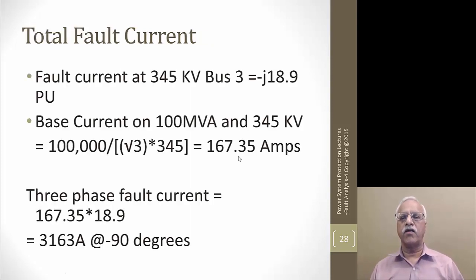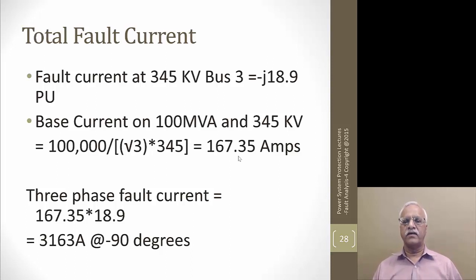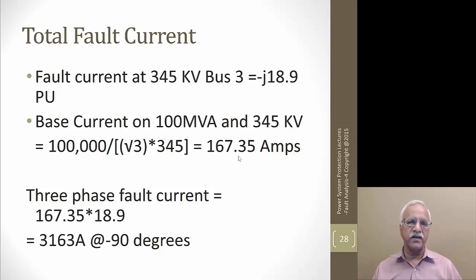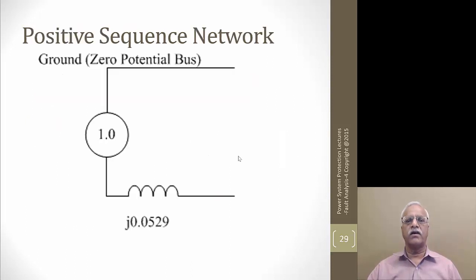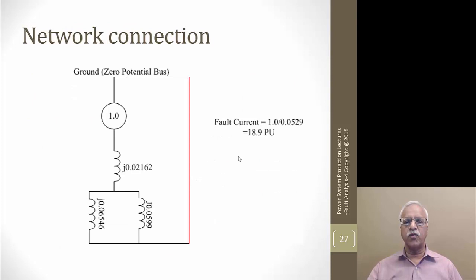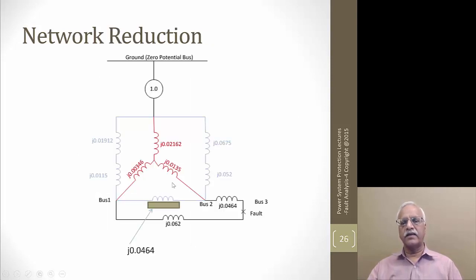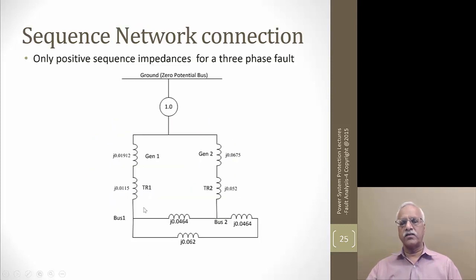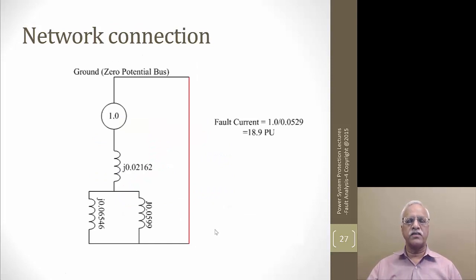The total fault current at 345 kV is -j18.9 per unit. The base current on 100 MVA at 345 kV is 167.35 amperes. So the three-phase fault current is 167.35 × 18.9 = 3163 amps at -90 degrees — lagging the voltage by 90 degrees because we neglected all resistances. To find the individual generator contributions, you use this current, make divisions in the network, then work backwards to calculate how the currents are divided between generator one and generator two, and convert back to phase currents.